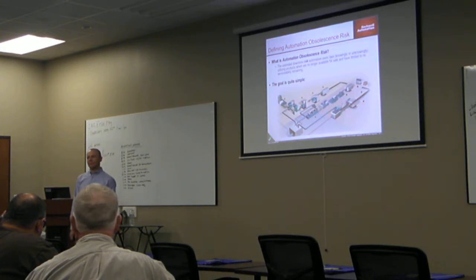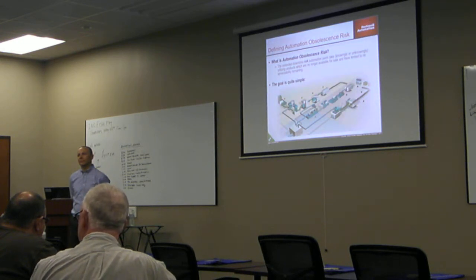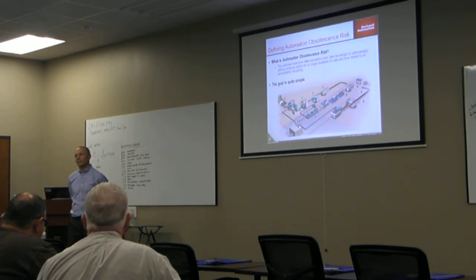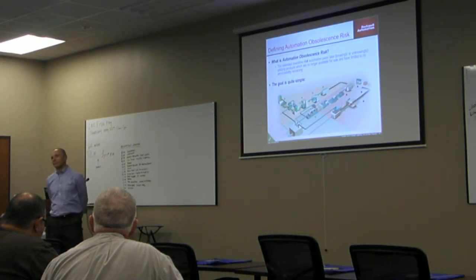And so if you're going through a lot of input modules, find out what's causing that input module to go out and upgrade that or whatever. If you're losing a lot of processors, because the PLC5, if you're losing input and output modules on a PLC5, that swing arm is falling apart. It's disintegrating, it's coming loose, and there's a lot of things like that. So it's about time to go ahead and upgrade. And if you're going from an older processor to another one, you are going to increase productivity, reduce downtime, and get more information back to the bean counters so they can get something out of it, and it's worth it. But I cringe every time I hear if it ain't broke, don't fix it.